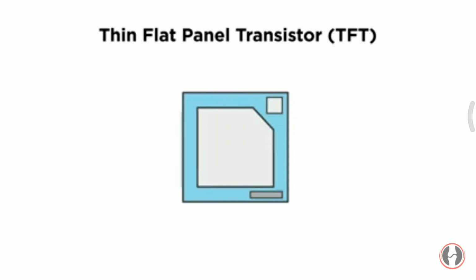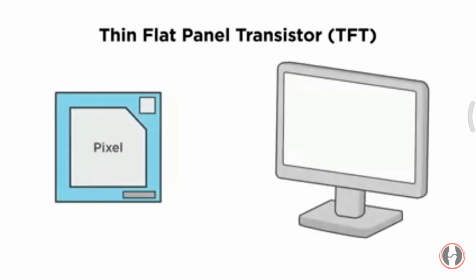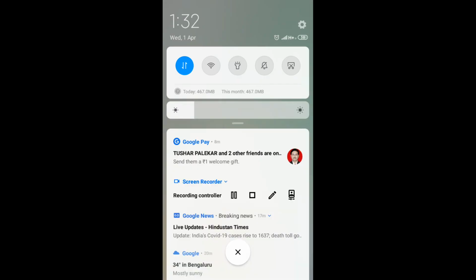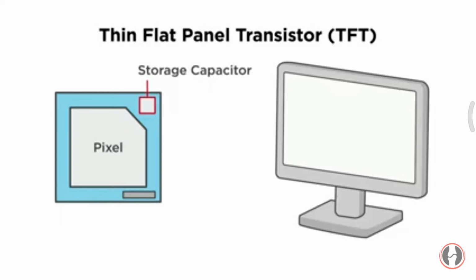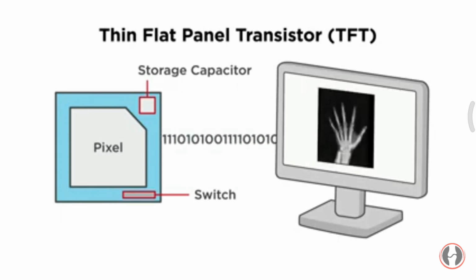Each DEL is comprised of a capture element or pixel detector, which is the active element within each DEL. A storage capacitor, which stores the electric charge produced by the capture element, and a thin film transistor or switch that acts to open and close the release of electric charge leaving each DEL, thus producing the digital image.